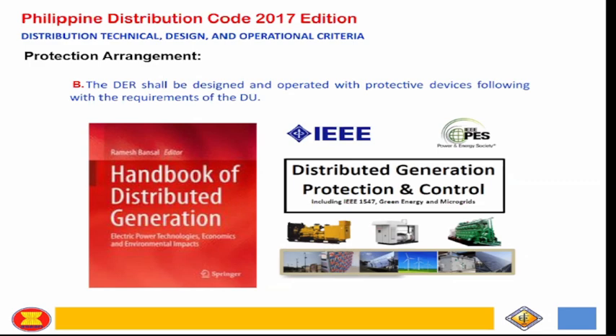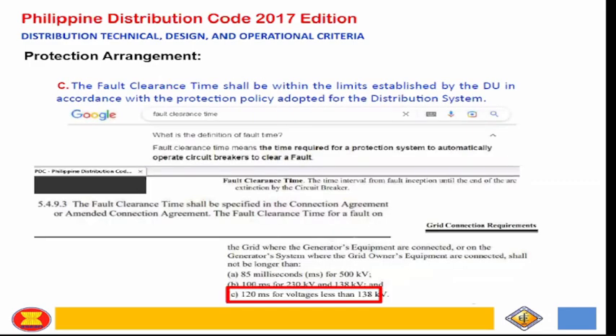So kailangan pag-usapan talaga. And then the fault clearance time shall be within the limit established by the DU in accordance with the protection philosophy adopted by the distribution system. So sa Philippine Distribution Code walang na-mention doon na clearing time, but in the Philippine Grid Code, PGC, yeah, may provision doon na 120 ms for voltages less than 138 kV. Kaya sa Meralco nga, yung ni-require sa amin is 100 ms.